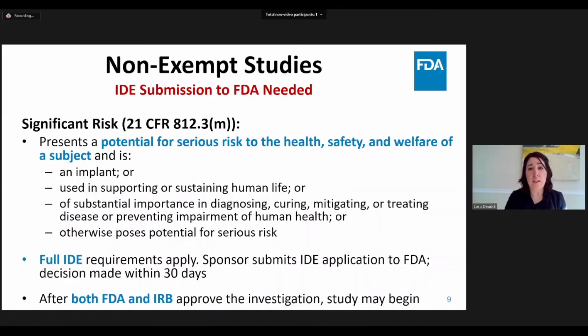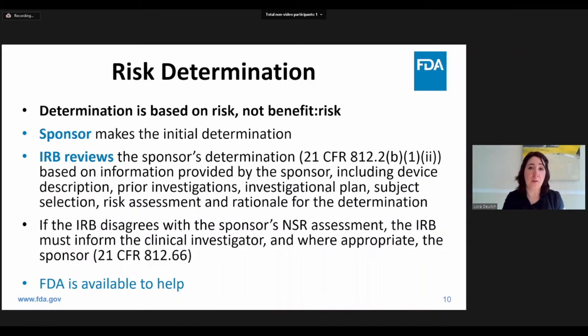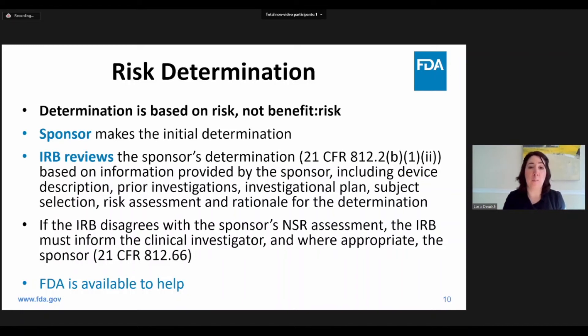A significant risk study can begin only after approval by both the FDA and the IRB. So how do you determine the risk of your study? The first thing to know is that a study risk determination is made based on the study's risk, not on the ratio of benefit to risk. It is also the risk of the study, not the device. Study risk determinations are initially decided by the sponsor. Based on the determination of significant or non-significant risk, you can then decide whether to go first to an IRB or the FDA for review and approval of the study.